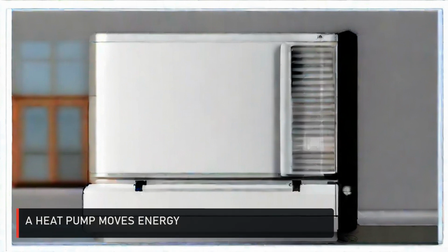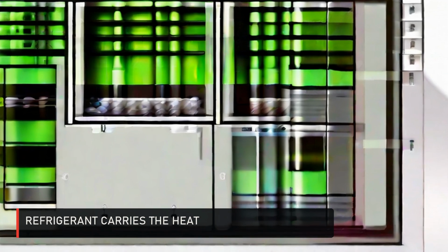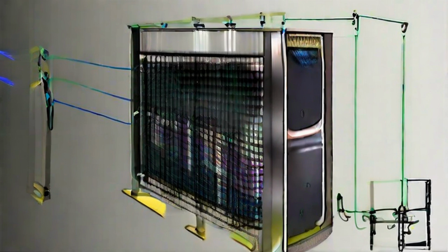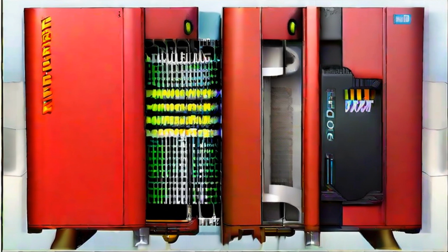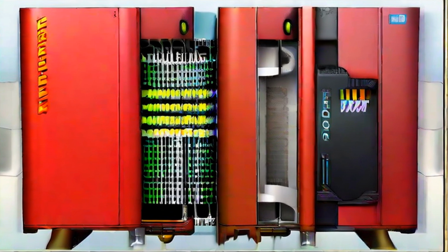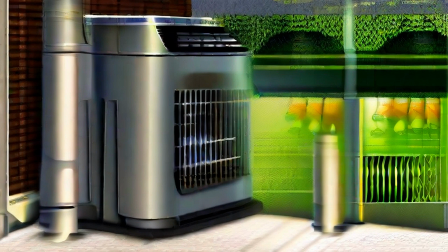A heat pump is closer to a refrigerator running in reverse than to a simple resistance heater. The refrigeration circuit uses a fluid designed to evaporate and condense at useful temperatures and pressures. At low pressure it absorbs heat while evaporating. After compression it can condense at a higher temperature and release heat indoors. Changing pressure lets the system move heat from a colder source to a warmer destination. Refrigerants have environmental, safety and engineering trade-offs, so systems are designed around specific fluids. Phase change lets the refrigerant act as a practical heat transport medium.